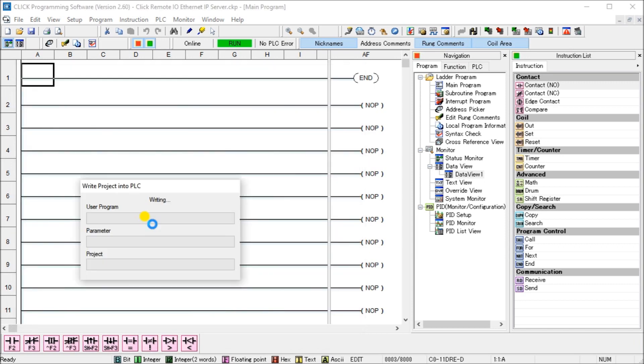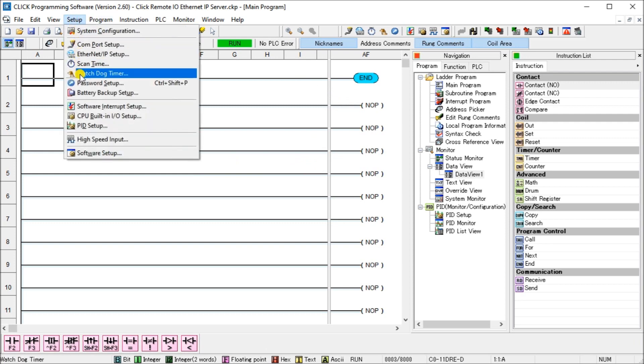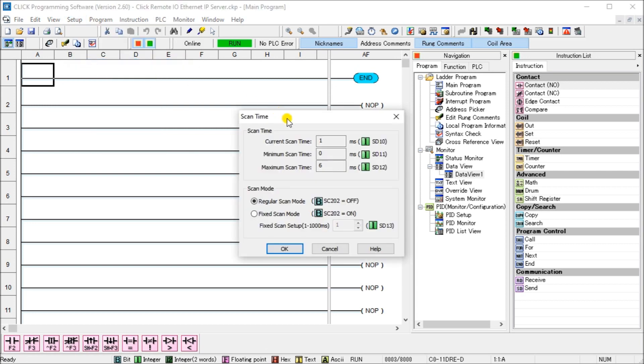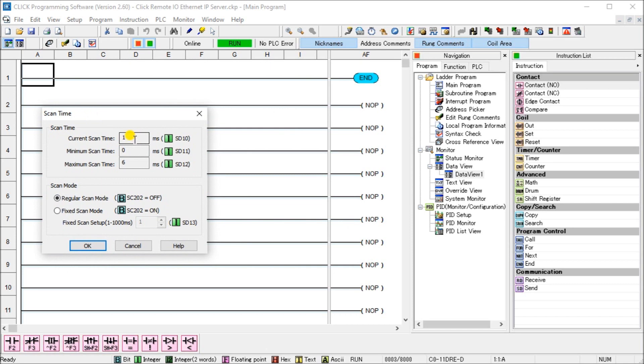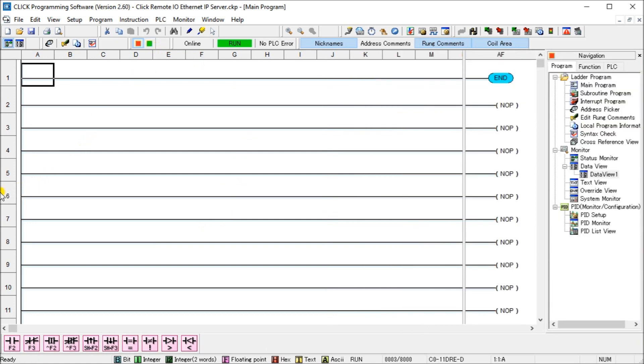Next we'll go to Setup and look at our Scan Time. Our current scan time is around 1 millisecond or less. Our minimum is zero and the maximum scan time ever reached was 6 milliseconds. So we're going to set our update time for this Remote IO to about 10 milliseconds, which will give us enough time to do all the communications we need. Our adapter is now set to run.